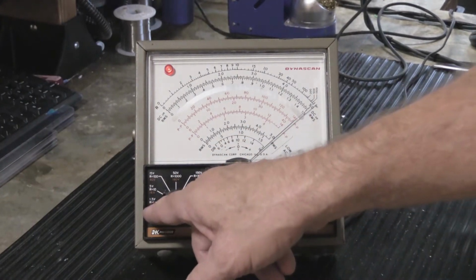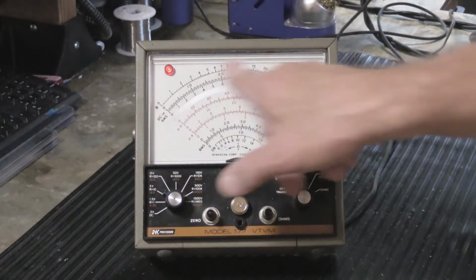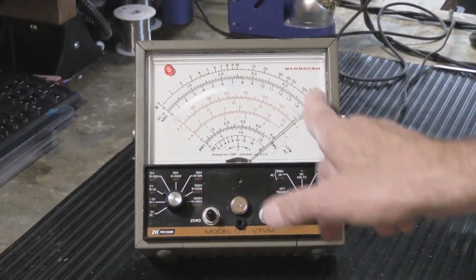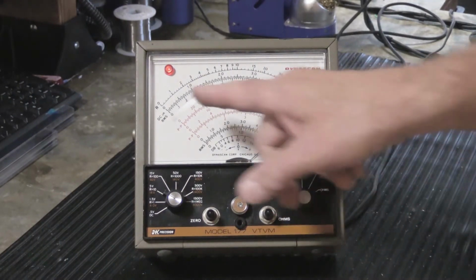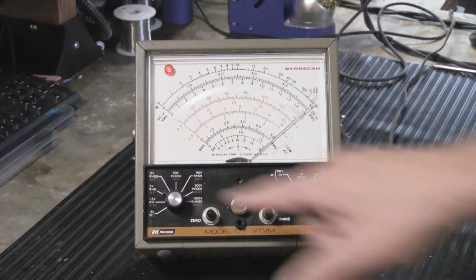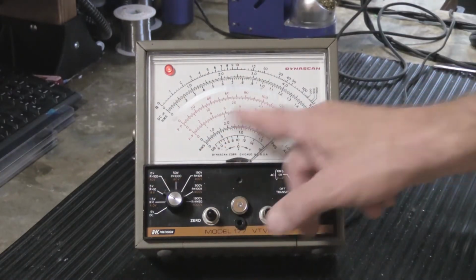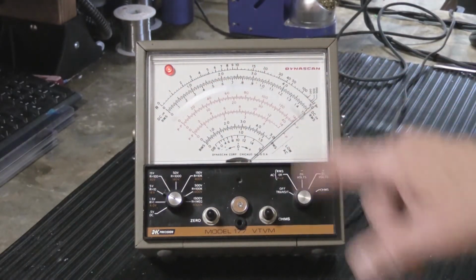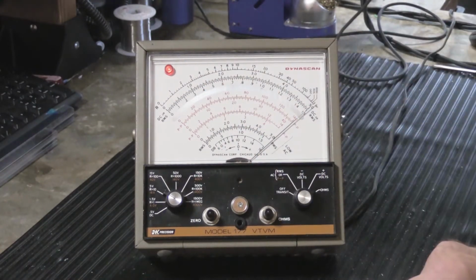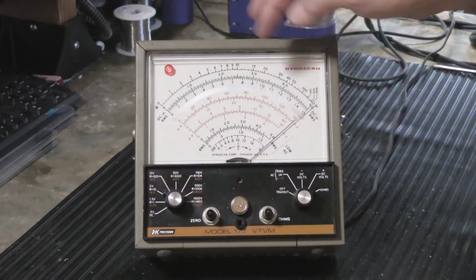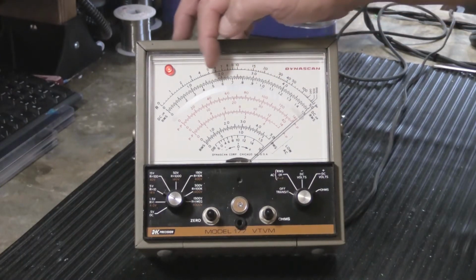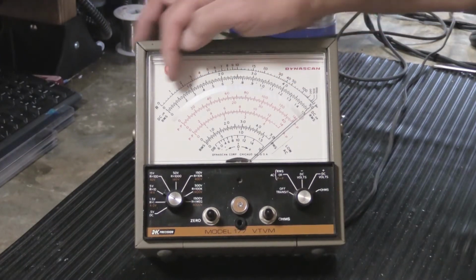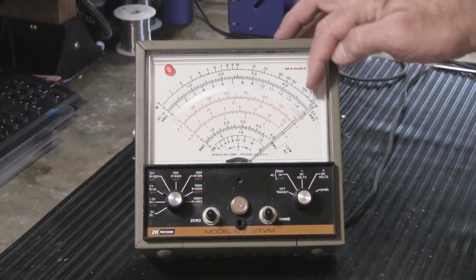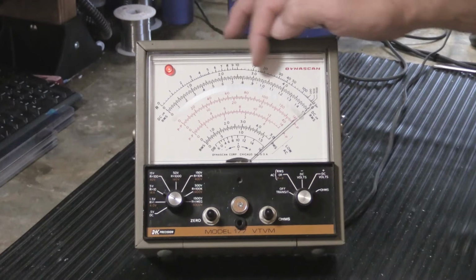So there are multipliers for resistance, because the range of the actual meter itself, the movement, is limited from here to here, so it doesn't go around and around and around. So it uses multipliers to keep the needle within the range of the actual scale itself. And when you use a meter like this, regardless of whether you're doing voltage or resistance measurements, you want to try to set up your ranges to keep the needle in the middle third of it. You don't want to be way down here, and you don't want to be way up here. You want to be kind of in the middle range, because this is where it's the most accurate.